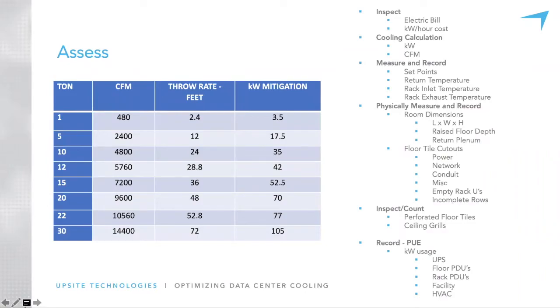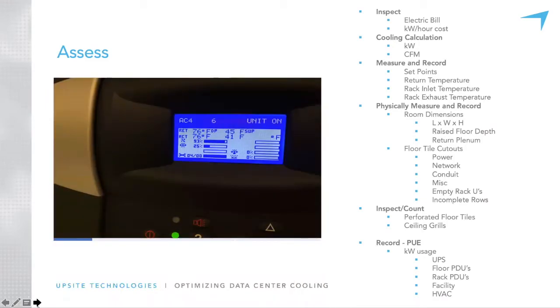All right, as we start to assess this facility, we want to keep this chart in mind as we're looking, again, both at the cubic feet per minute that we need to supply, and also at the IT kilowatt load and what's required from there. We're going to start with the very basics. We're going to get our cooling calculation in kilowatts and cubic feet. We're going to see where the set points are, return temperatures, rack inlet, the rack exhaust. We're going to look at the room dimensions. Is there a plenum?